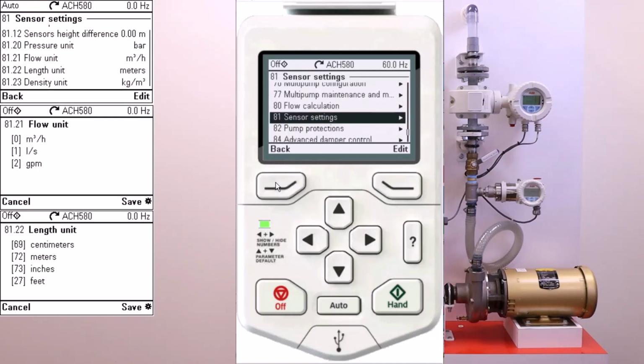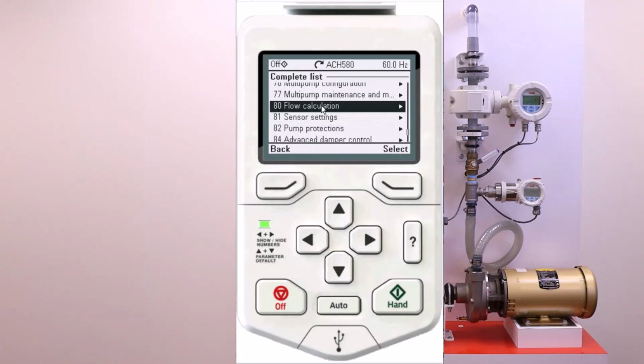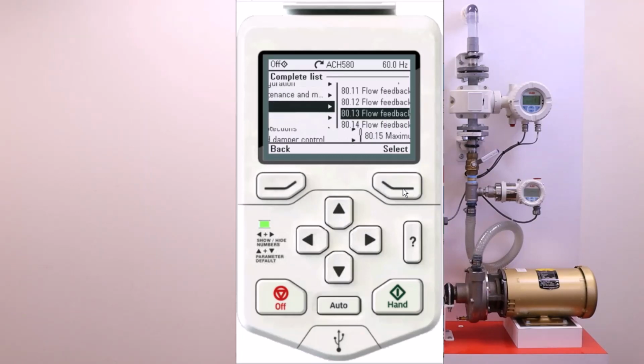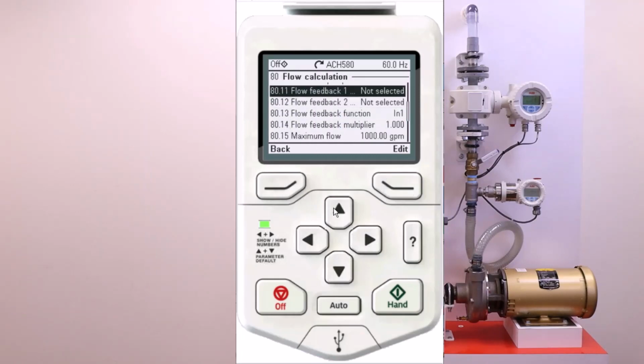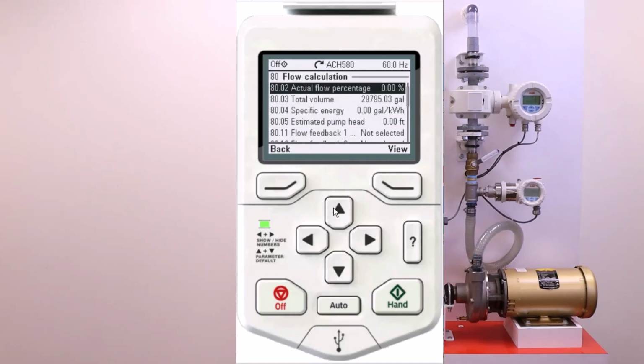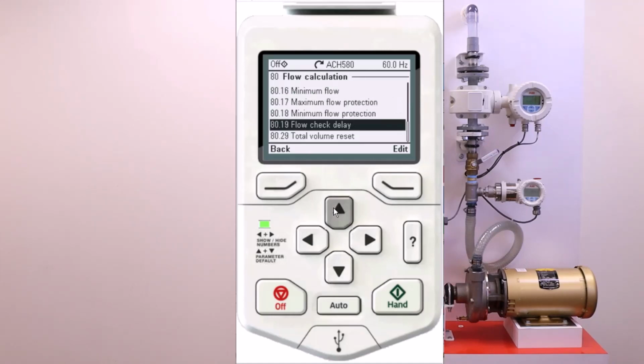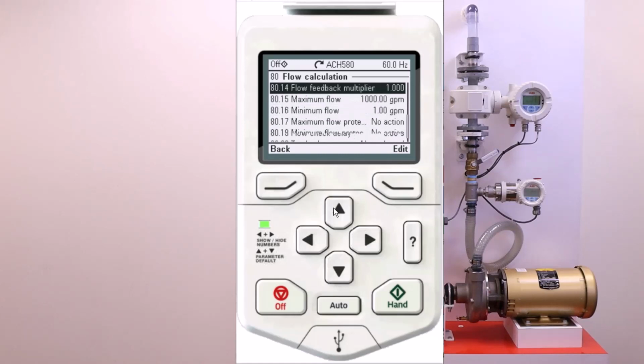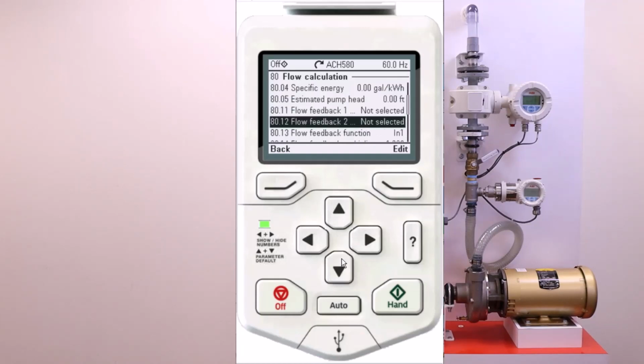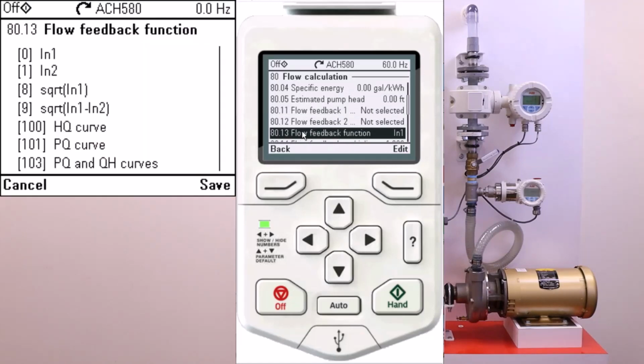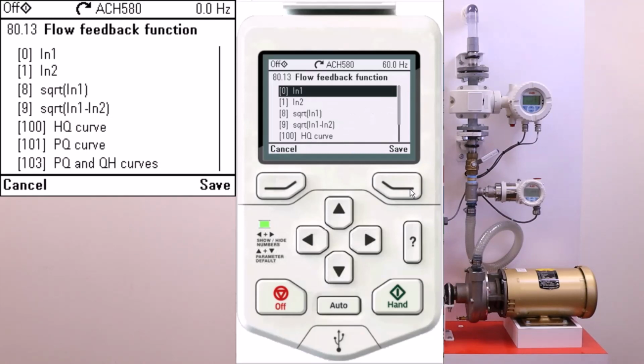Okay, I can back up and I can go to Group 80 now. Alright, I come up in Group 80. I select Group 80. In Group 80, we have multiple different parameters here. If you look at it closely though, there's no parameters in Group 80 that will support entering in our chart data. That's because we need to set it up for sensorless pumping. And that means we're going to need to go to 80.13 flow feedback function. If I go into edit here, here's my options for flow feedback function in Group 80.13.